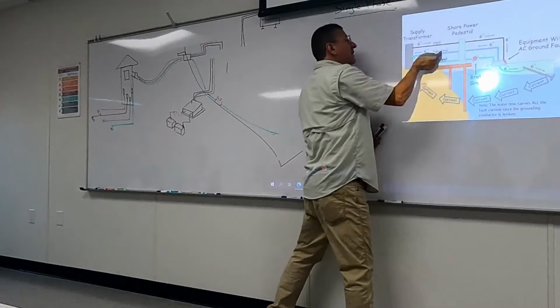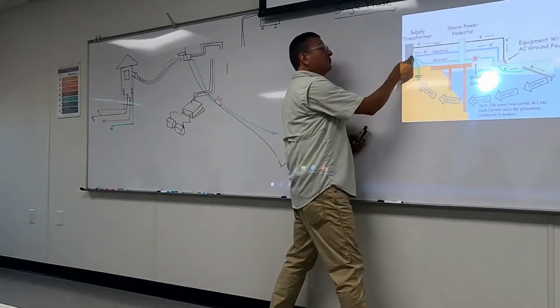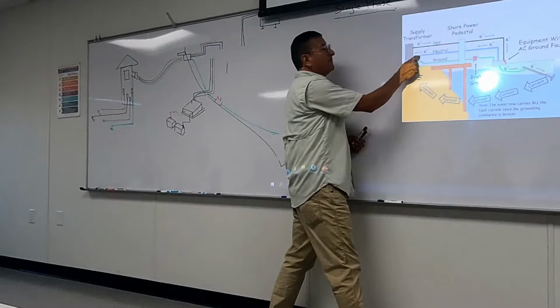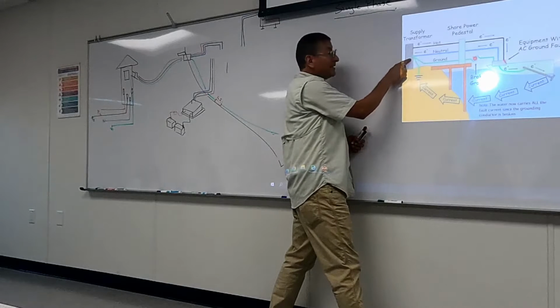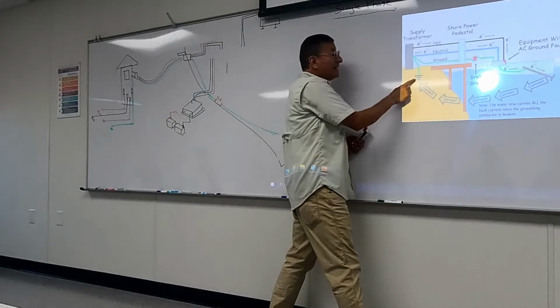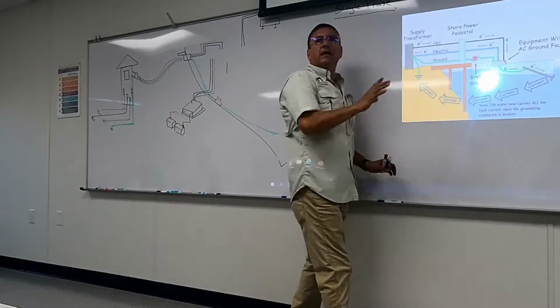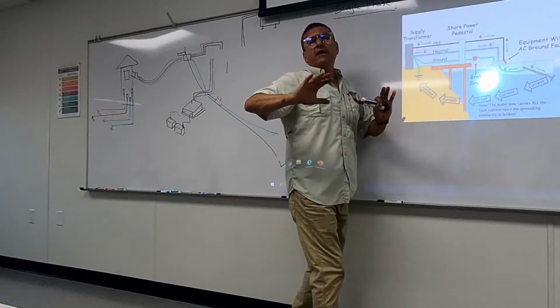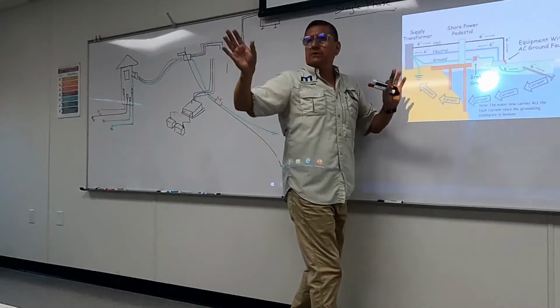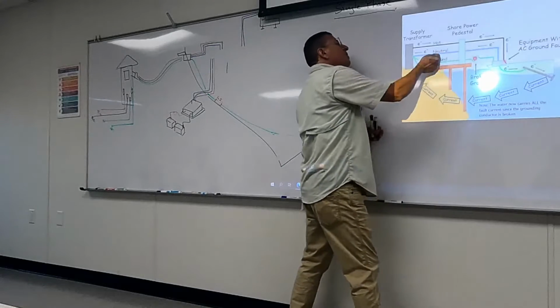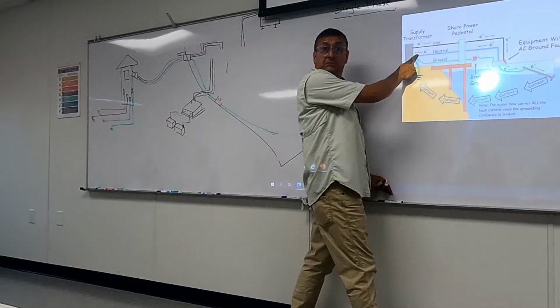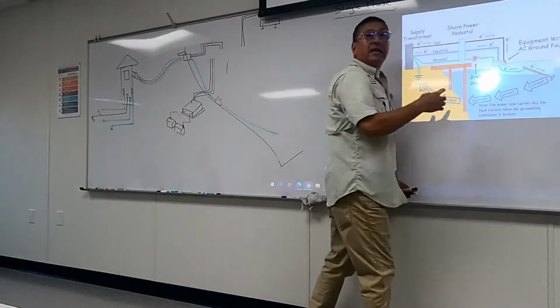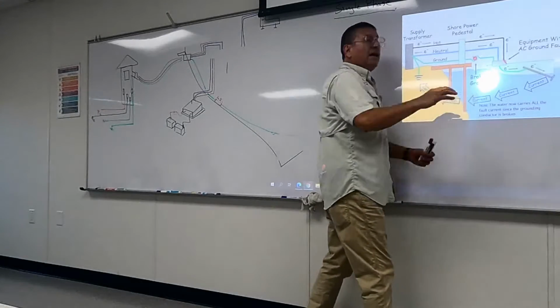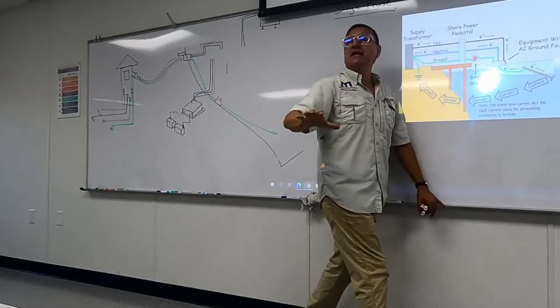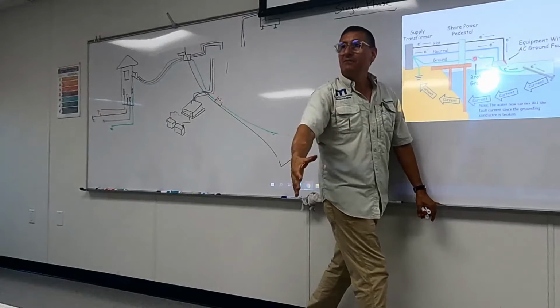It returns through the neutral into the source of the power, because only at the source of the power are both of them connected together - this is the source of the power, and this is the ground. In this moment I have an excess of current, 10 amps, and those 10 amps return here. And additionally, static electricity is drained to the ground.